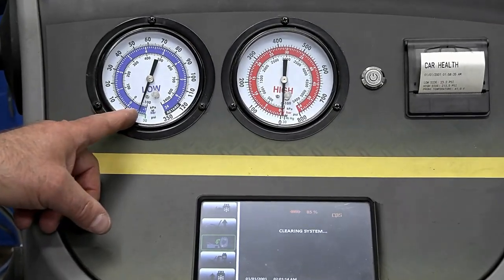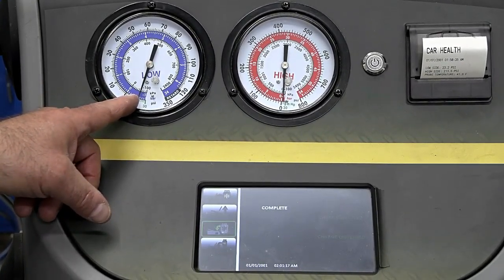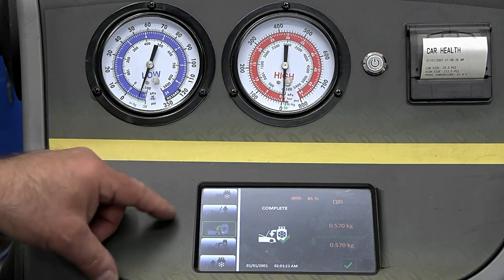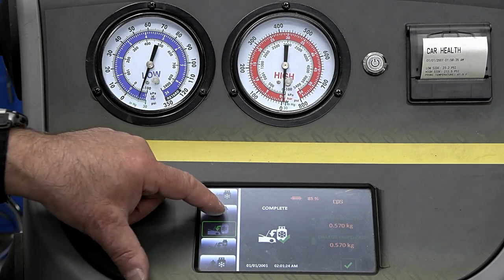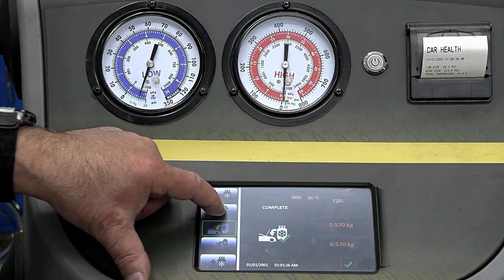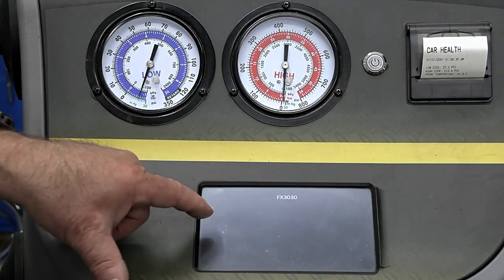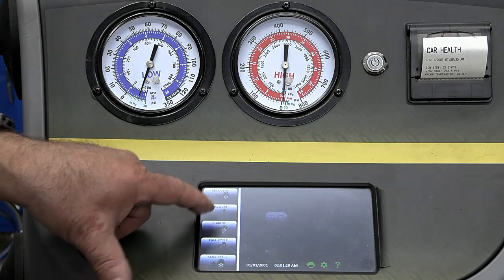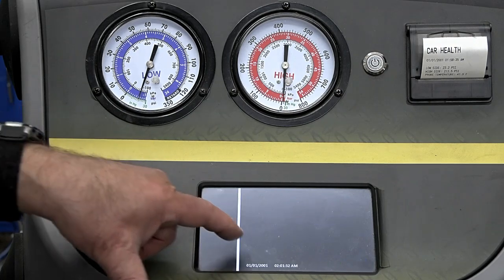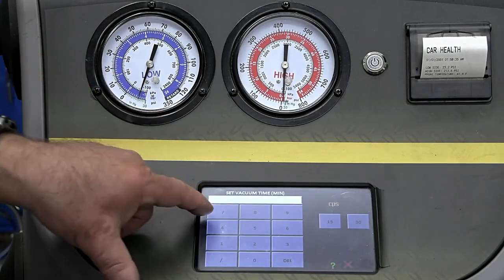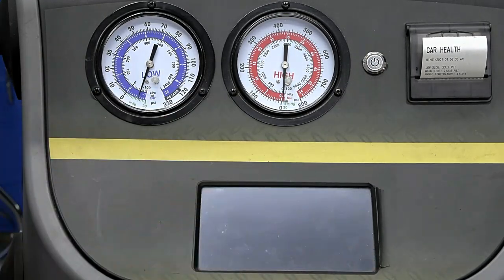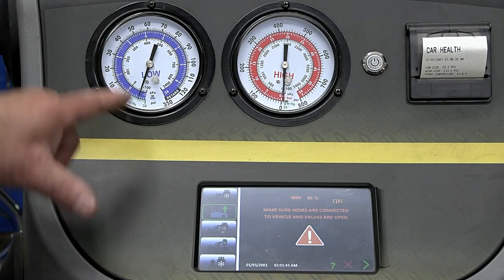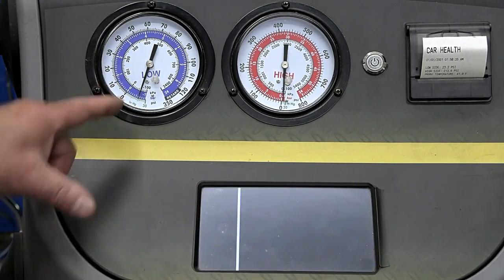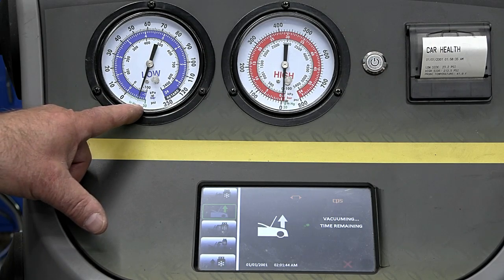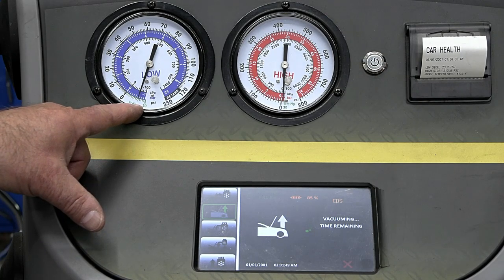When it's done clearing, notice it didn't go all the way down into a vacuum. So what I do is I want to make sure my machine doesn't have a problem. I'm going to hit the OK key, then hit vacuum. All you got to do is put it on for less than a minute just to get this gauge all the way down. Okay, and now it'll suck it down to 29.9 or 30. That way, when we're down there, we know if we have a problem or not.